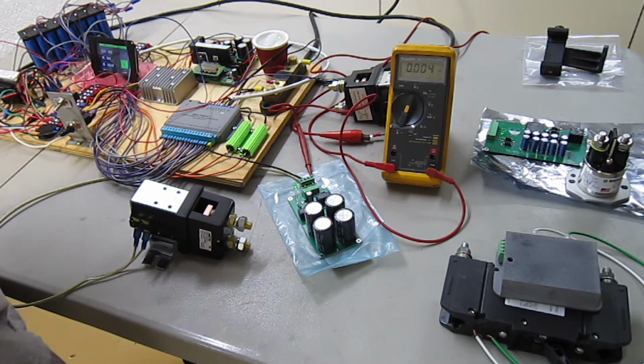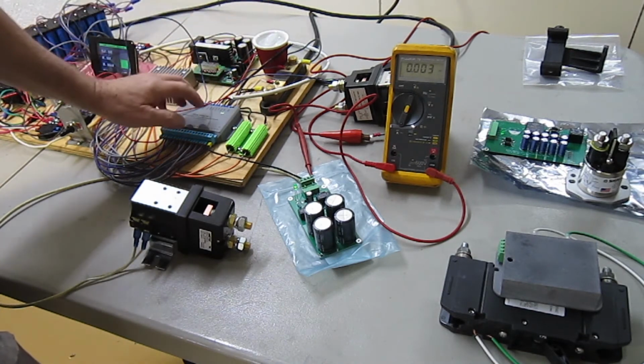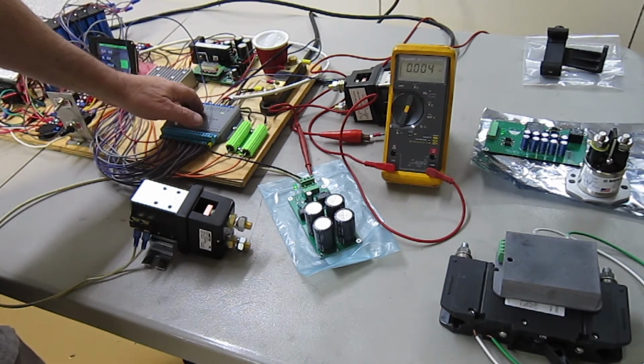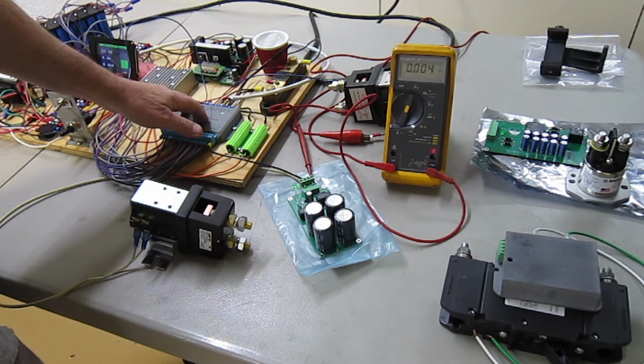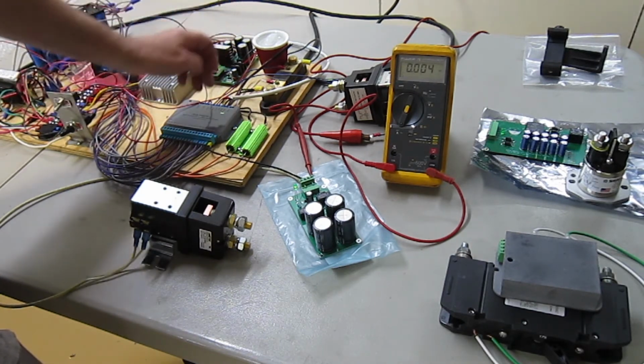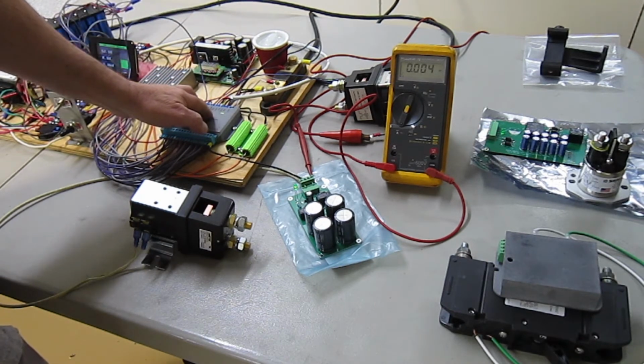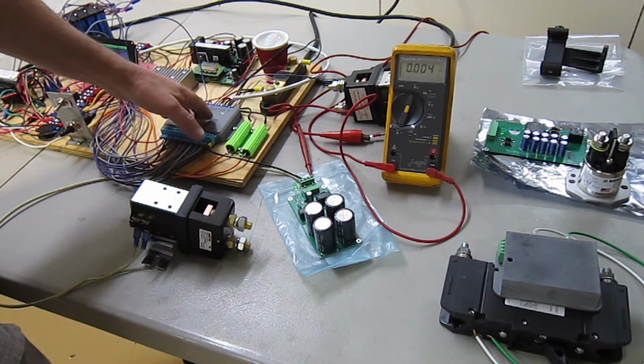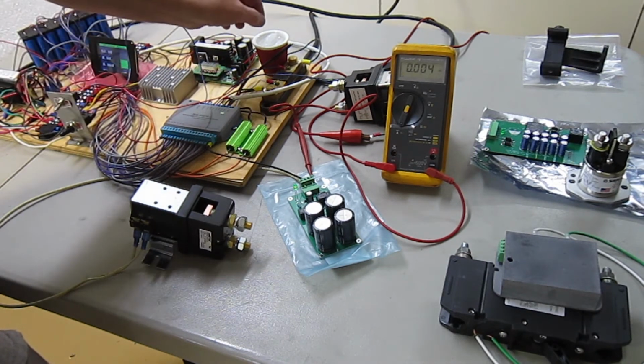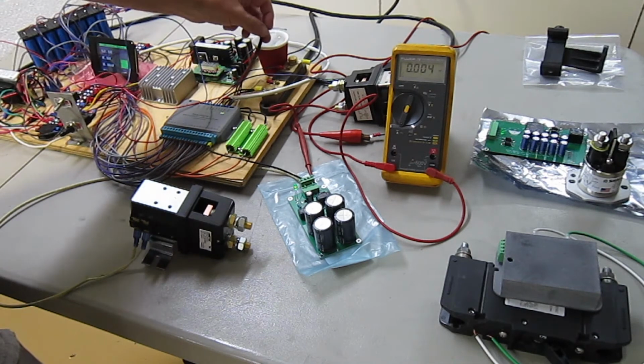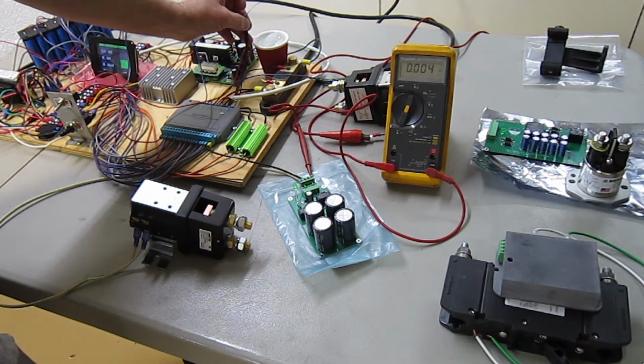And just to keep me honest, this has a photo relay on it, a type of solid state relay versus the switch. This would be typical of many BMSs that use an external contactor. I'm going to use ice water to simulate a cold condition.